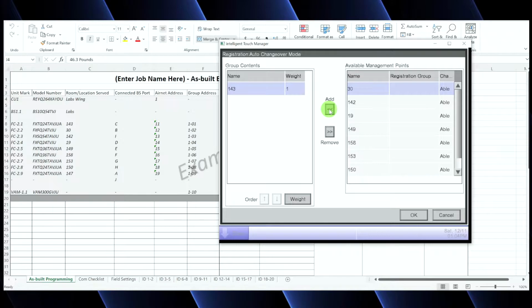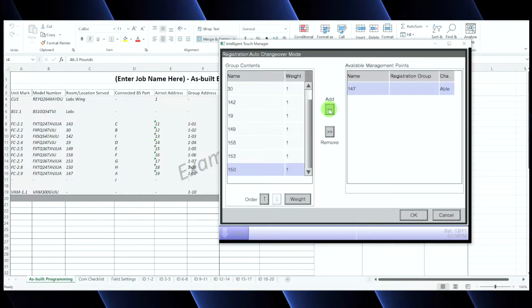Now, what I'm going to do is simply click that add button, and you'll see that all of the units on the right are moving over to the left. If for some reason there was a unit that you did not want to be in auto, for example, let's just pretend this FXTQ24 FCU or FC 2.3 was in a server room and that was a cooling only unit. Well, we wouldn't want that unit to be part of our changeover group. So in that instance, we'd want to make sure that we remove that unit 142 from our auto changeover group. That way, when we program in that auto mode, it doesn't affect 142, that server room. In this particular case, we don't have any server room units. I was just using that as an example.